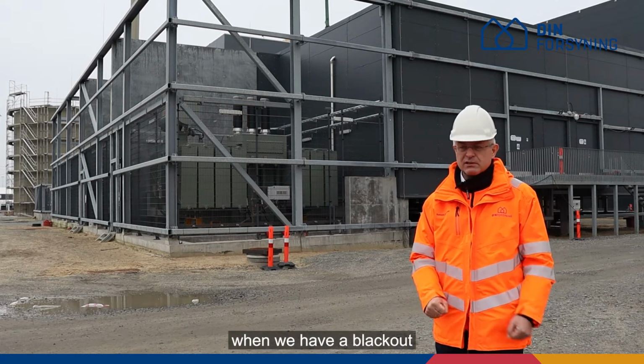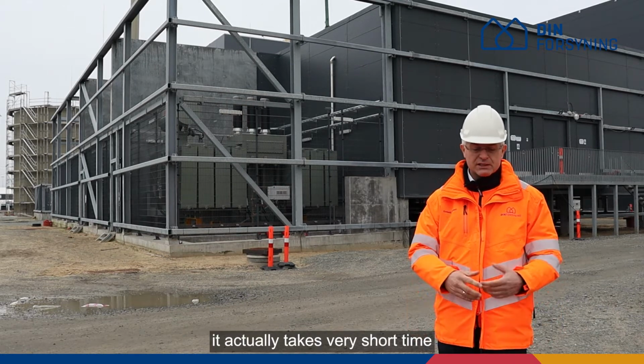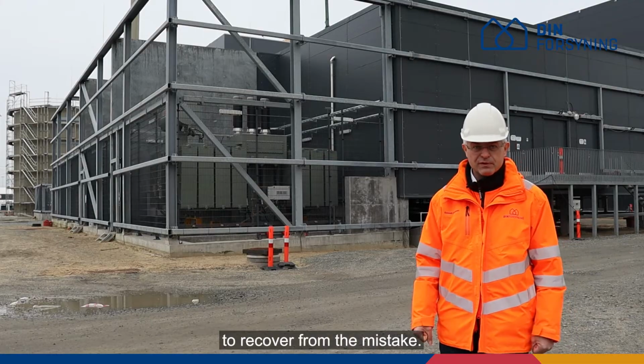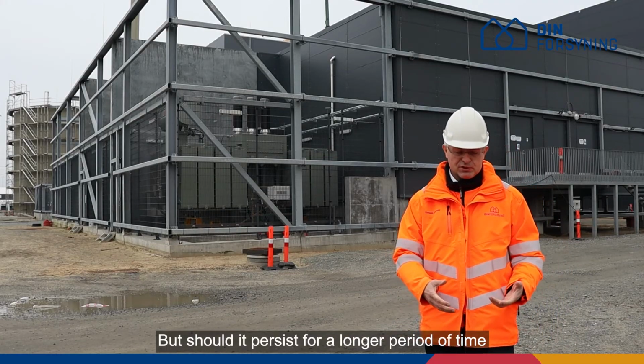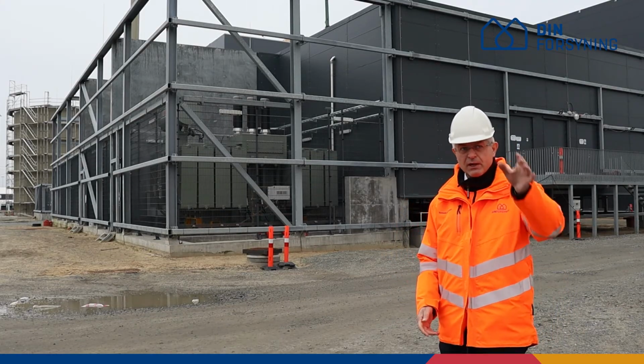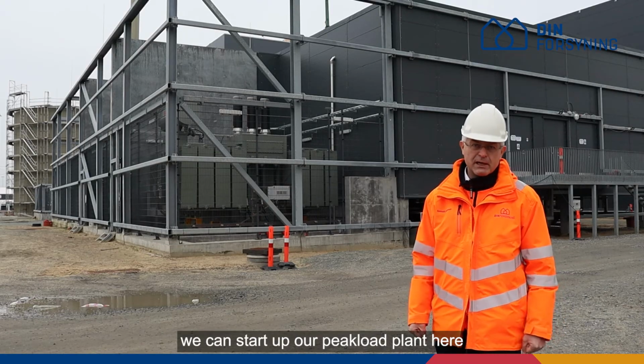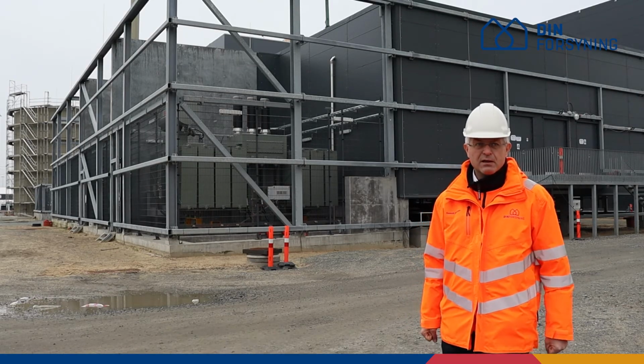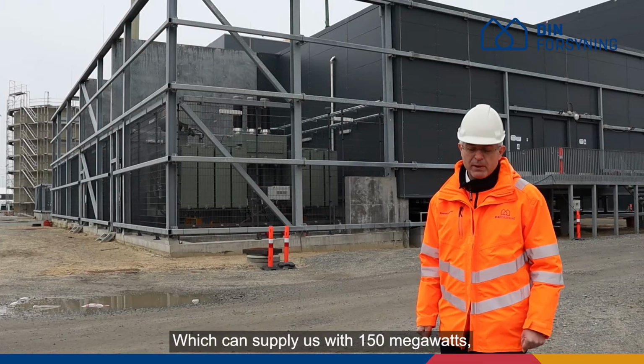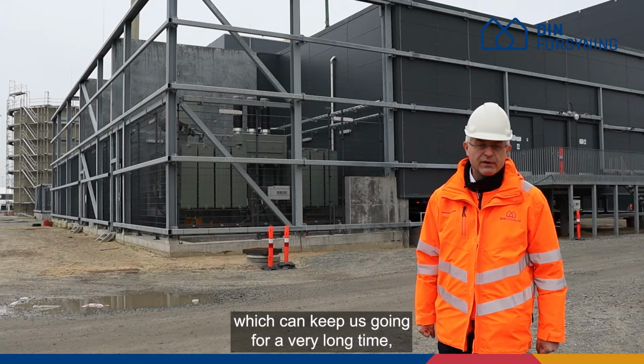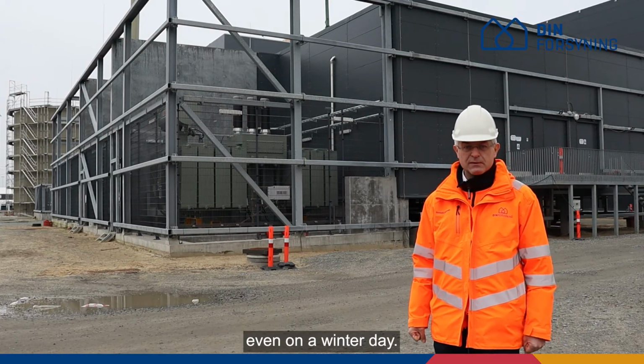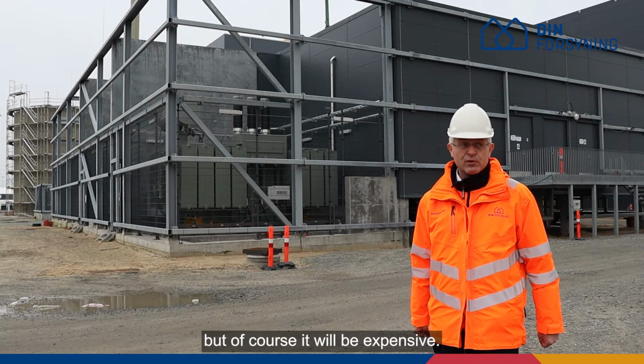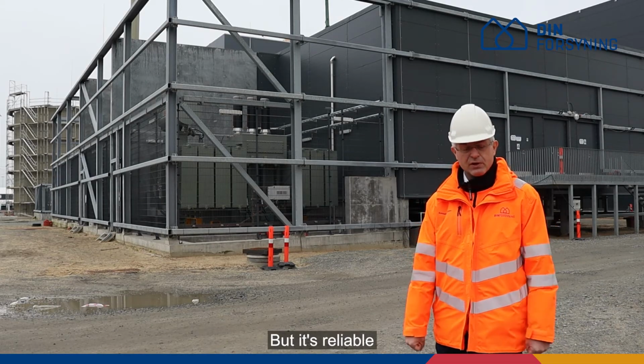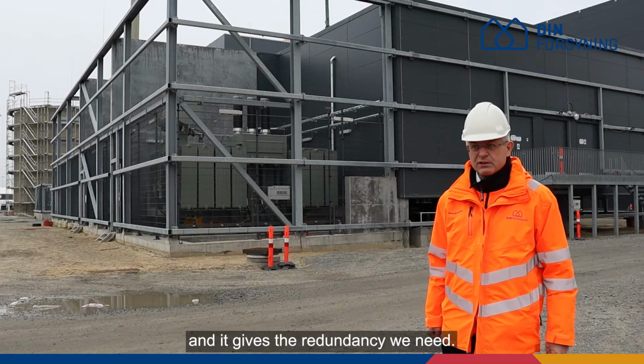So in most cases when we have a blackout, it actually takes very short time to recover from the mistake, but should it persist for a longer period of time, we can start up our peak load plant here, or emergency plant, which can supply us with 150 megawatts, which can keep us going for a very long time, even on a winter's day. So that's why we have sized it, but of course it will be expensive, but it's reliable and it gives the redundancy we need.